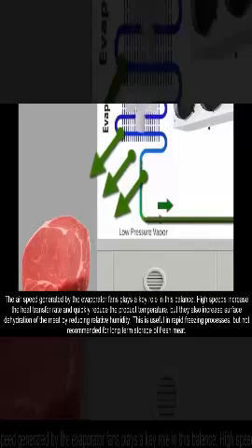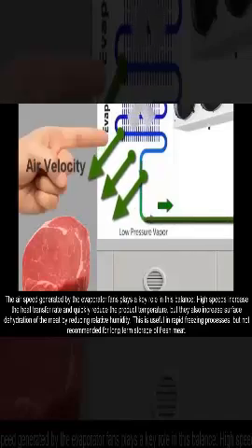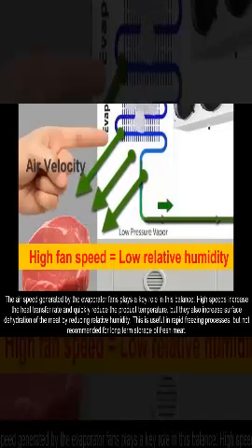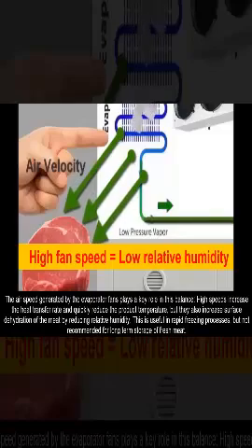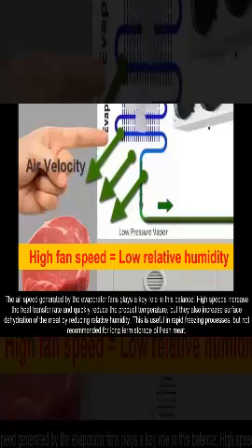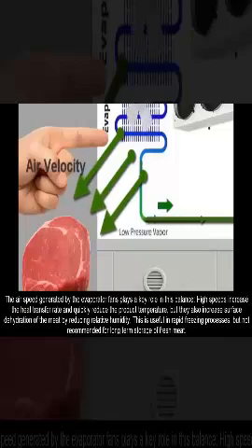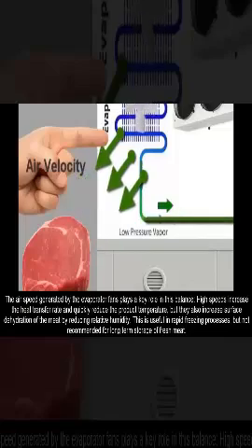High speeds increase the heat transfer rate and quickly reduce the product temperature, but they also increase surface dehydration of the meat by reducing relative humidity. This is useful in rapid freezing processes, but not recommended for long-term storage of fresh meat.